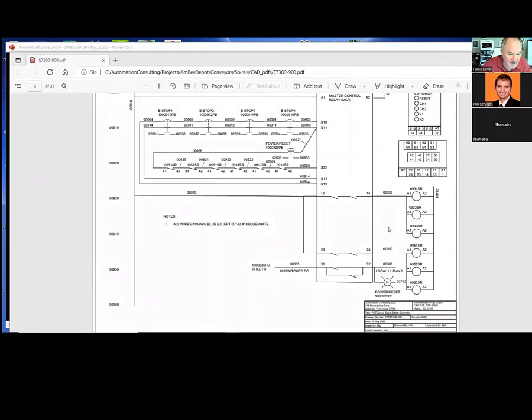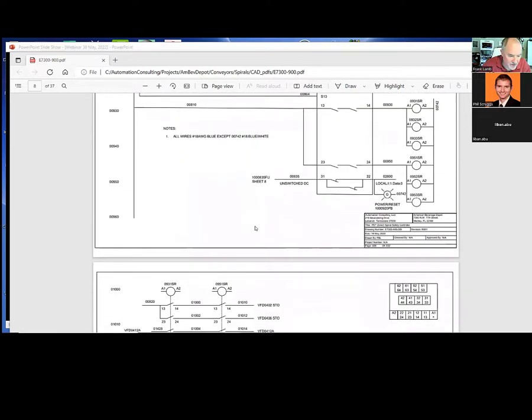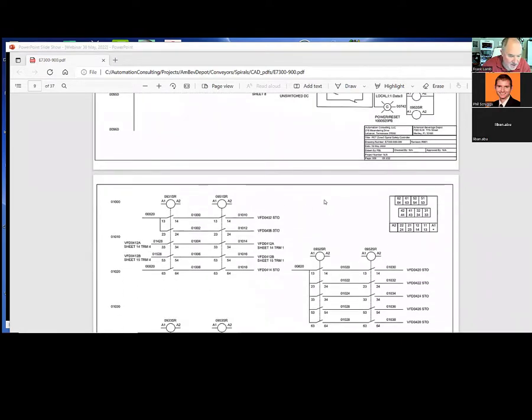Back to the safety side, there's a lot of safety stuff here: e-stop 1 through 4, and there probably will be a light curtain too that I'll add later. What these do is remove power from the drive. So if you hit the e-stop, these safety relays will remove power from the drives, pushers, and things like that. It's all a safety function.